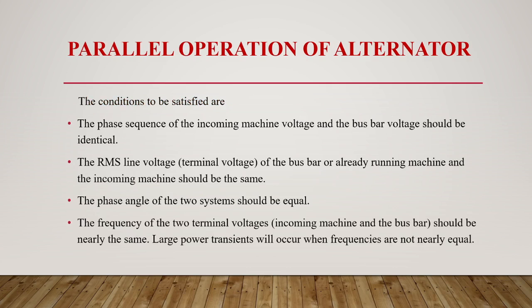So what are the conditions to be satisfied? Let us see now. The phase sequence of the incoming machine voltage and the bus bar voltage should be identical. The RMS line voltage of the bus bar or already running machine and the incoming machine should be the same. The phase angle of the two systems should be equal. The frequency of the two terminal voltages, that is the incoming machine and the bus bar voltages, should be nearly the same. Large power transients will occur when the frequencies are not nearly equal.